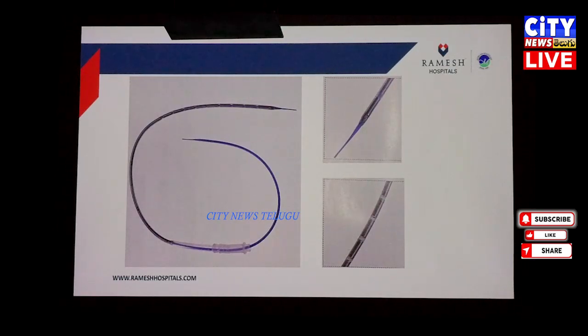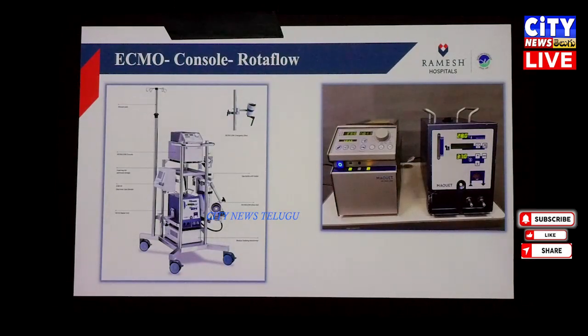These are classical venous cannula. They are long in length, generally 55 centimeters, and they will have multiple openings, not only at the tip, but also multiple side holes. These are primarily done so that there is better venous drainage into the circuit. This is how a console looks.